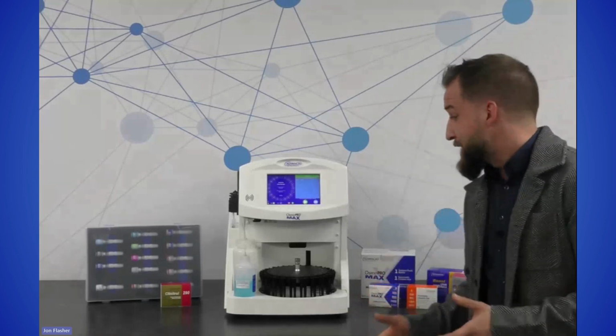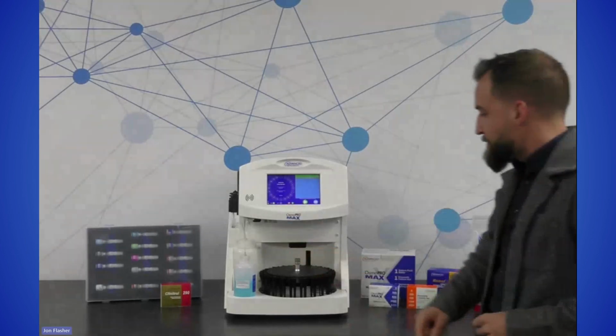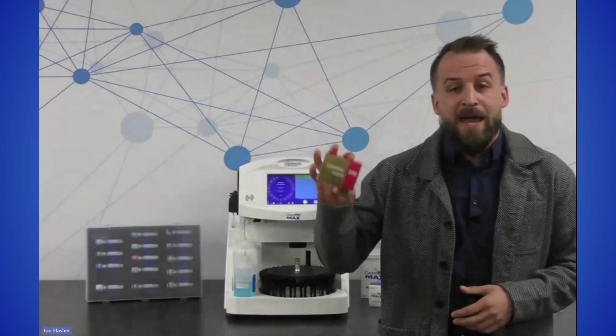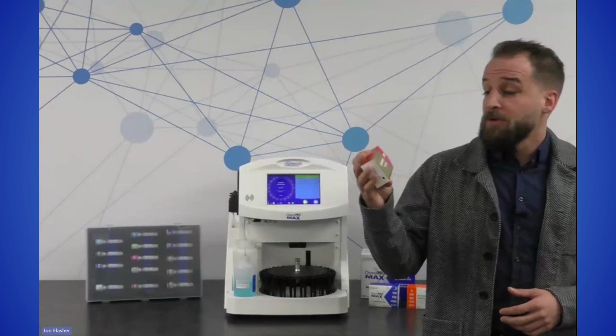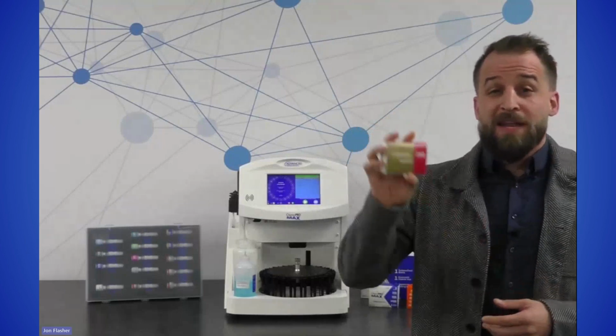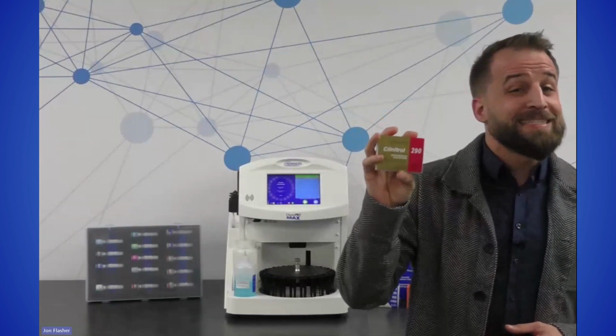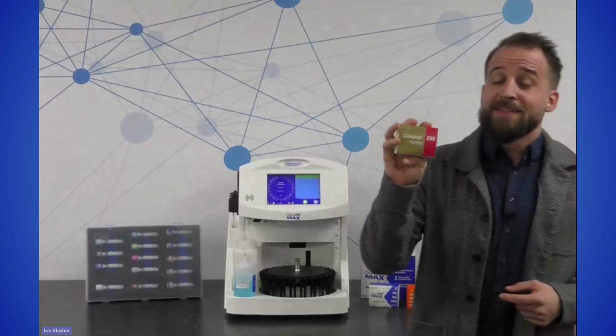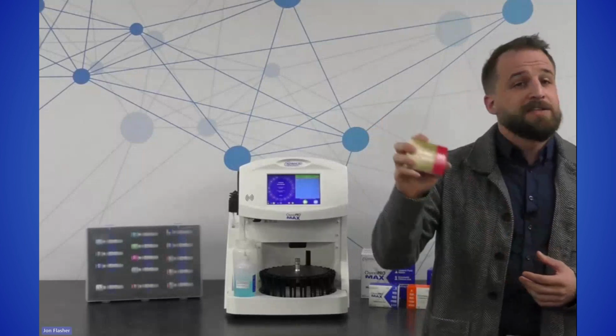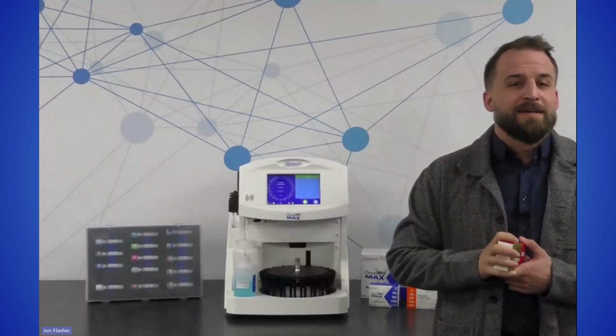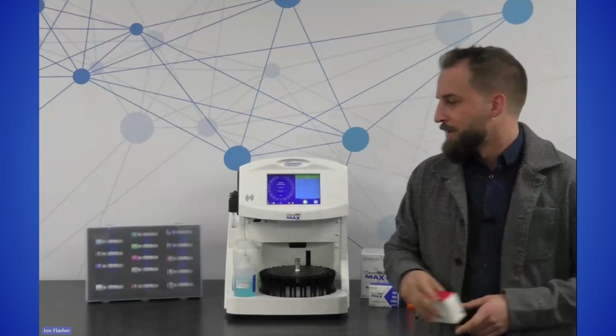So that said, I want to take a look at these over here. Another thing that you're going to need for the regular use of the OsmoPRO MAX is this Clinitrol 290. This is our daily calibration verification reference solution. It will be run at the beginning of every day at a scheduled time, and I'll show you what that looks like. And you actually can't run any tests unless you run this test at the scheduled time. So we'll get into some more details around that later in the demo as well.